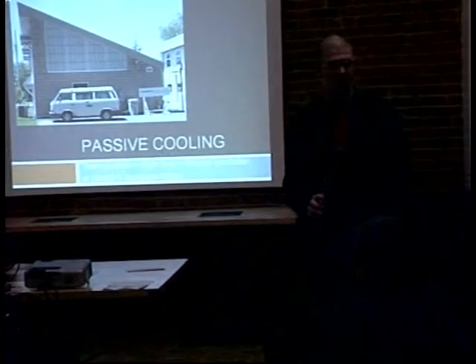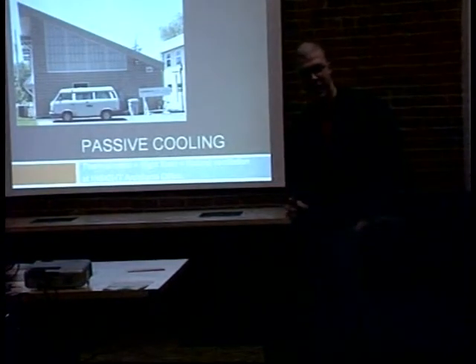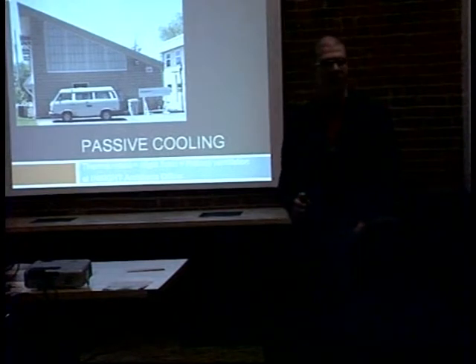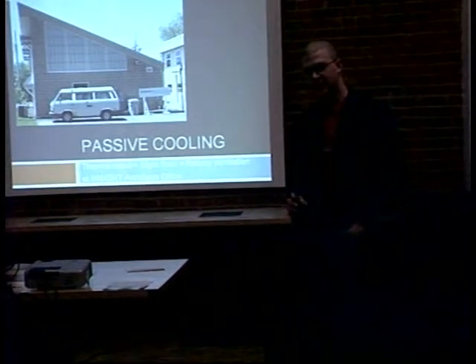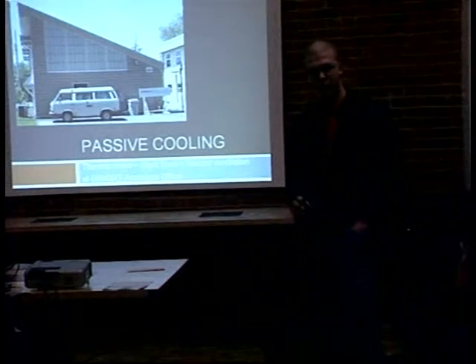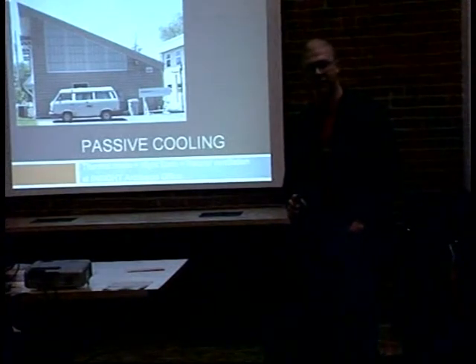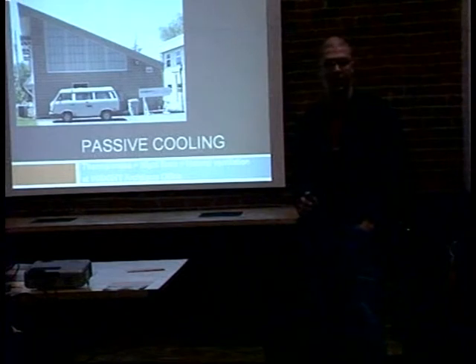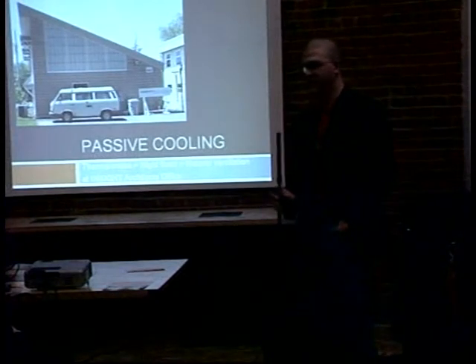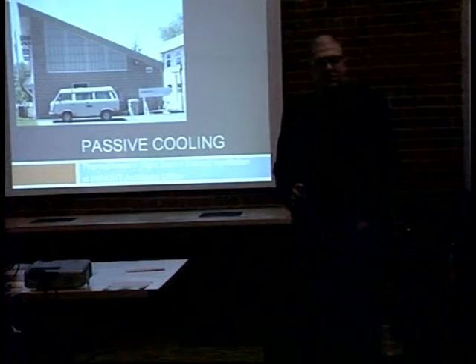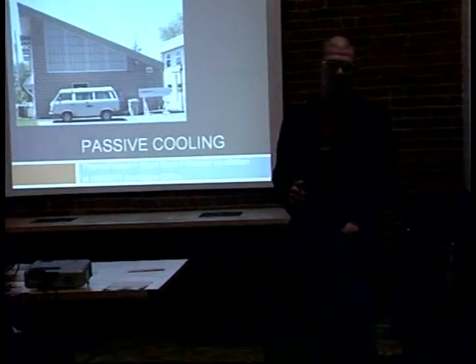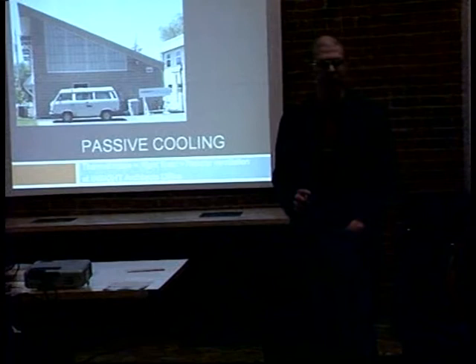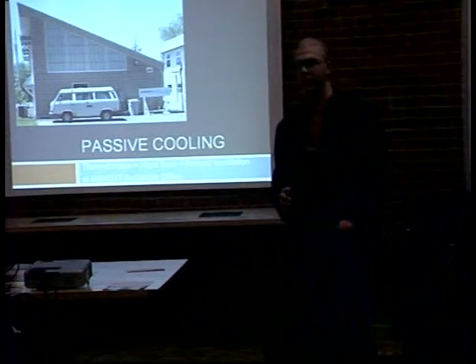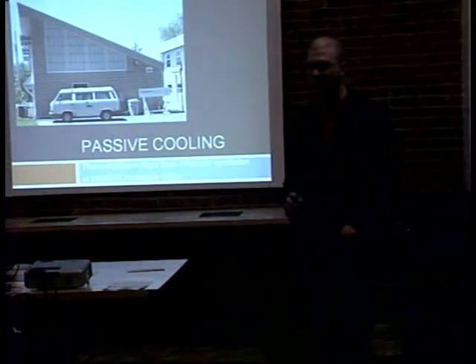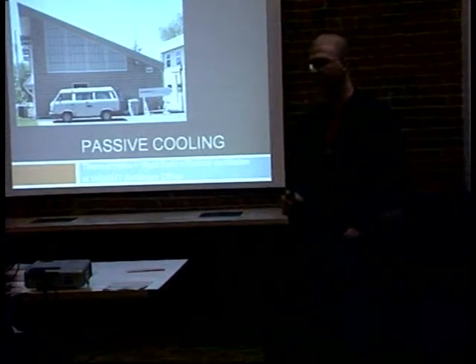One thing that comes up in conversations about natural ventilation is being careful not to hold it to a higher standard than we hold any ventilation system, whether passive, hybrid, or full mechanical. Because it's the exception rather than the norm that we're doing a high level of filtering on our supply air. So basically the best air we have to deal with is the air that's outside, whether it's pushed through pipes or ducts or comes through a window - you're dealing with more or less the same air. Now there are real issues with natural ventilation, like security.